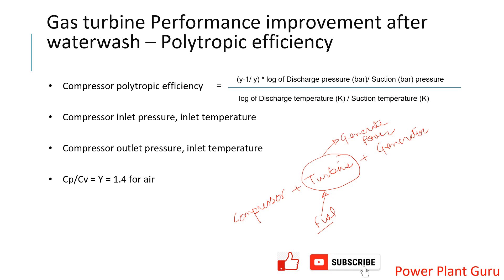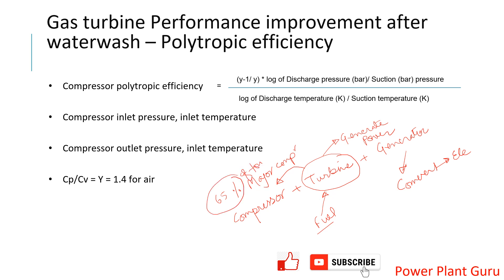Fuel energy is converted into power by the turbine. The generator then converts that mechanical power into electrical energy. However, not all the power generated by the turbine goes to the generator — the major consumption is in the compressor. Approximately 65% of the total power goes to the compressor. So if a turbine generates 100 megawatts, 65 megawatts goes to the compressor and only 35 megawatts is available for the generator.